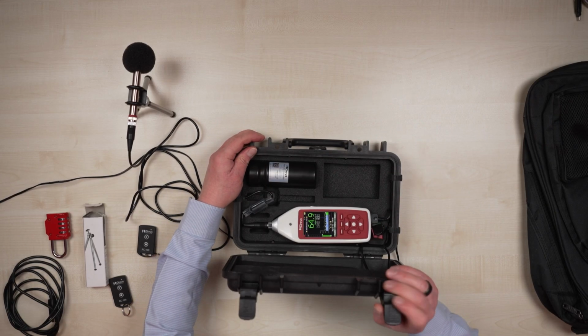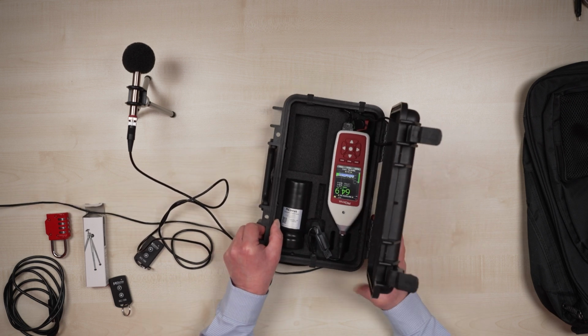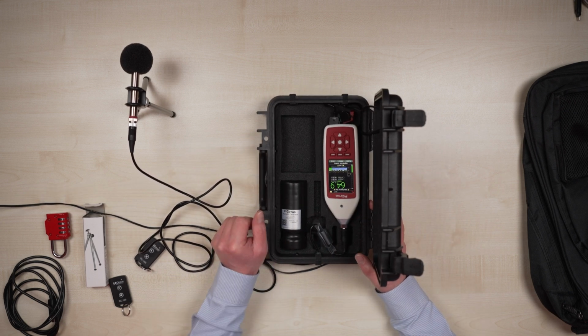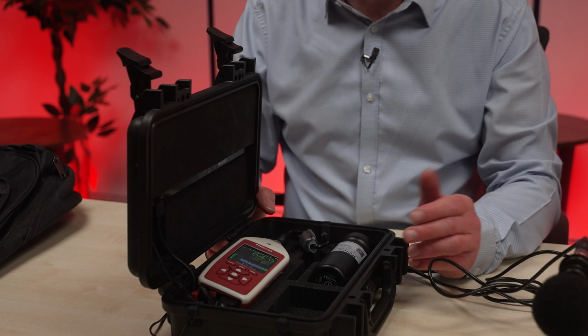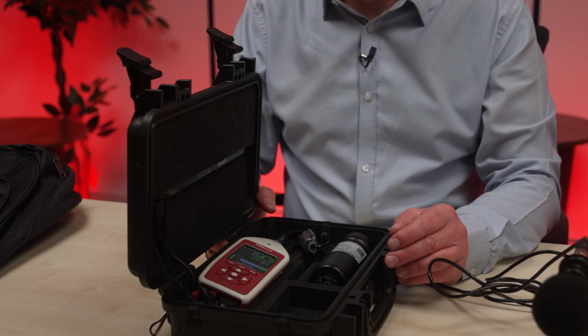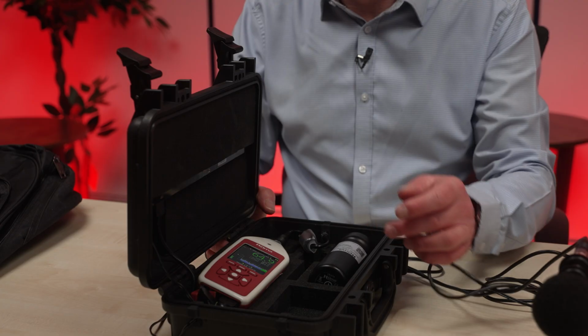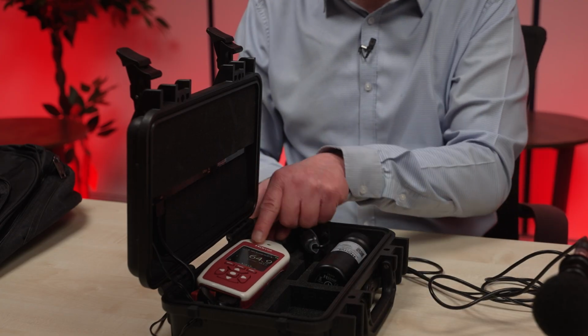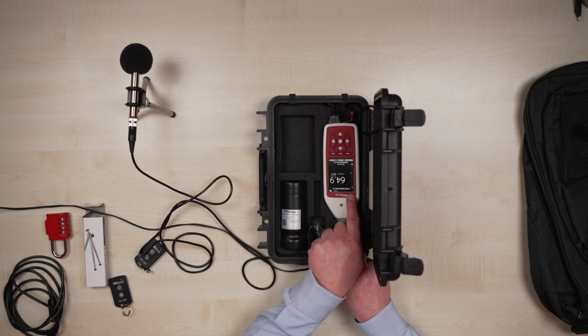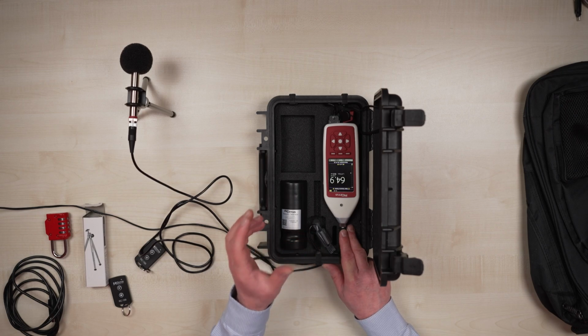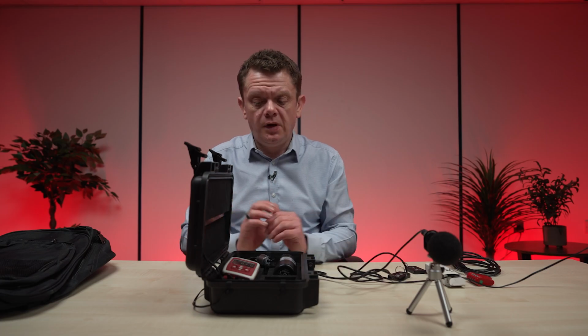In keeping with the button use earlier, calibrate to calibrate, start to start, when you're ready to stop your instrument, press the button that says stop. As soon as you've done that, the red circle disappears from the top of the screen, and you know your measurement has ceased. Our equipment does not have a save button, so you do not need to press save. As soon as you press stop, it's automatically stored onto the internal memory.